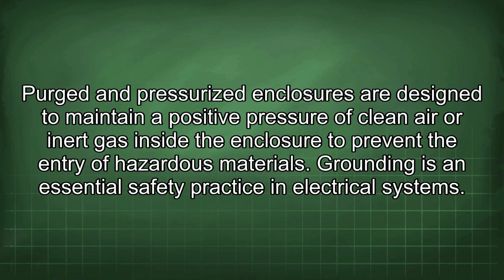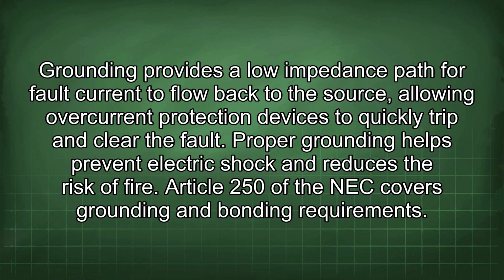Purged and pressurized enclosures are designed to maintain a positive pressure of clean air or inert gas inside the enclosure to prevent the entry of hazardous materials. Grounding is an essential safety practice in electrical systems. Grounding provides a low-impedance path for fault current to flow back to the source, allowing overcurrent protection devices to quickly trip and clear the fault. Proper grounding helps prevent electric shock and reduces the risk of fire.